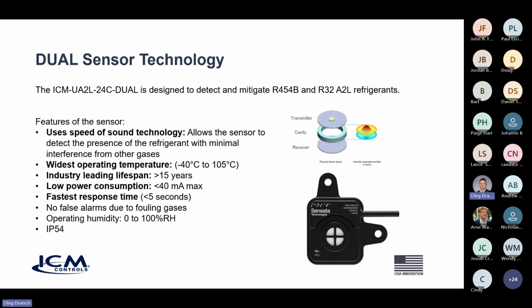And really a low power consumption. This is not a power-hungry device. And the response time, so under 5 seconds, again, tops in the industry. So that's another thing to give you peace of mind. And no false alarms, so it's not going to detect any type of coil overspray or any type of chemical that it shouldn't, right? It's going to detect A2L refrigerant, and again, it uses a technology that nobody else is using to do that. You've got a full spectrum of operating humidity, 0 to 100% relative humidity, and the device itself is IP54 for dust and water ingress.